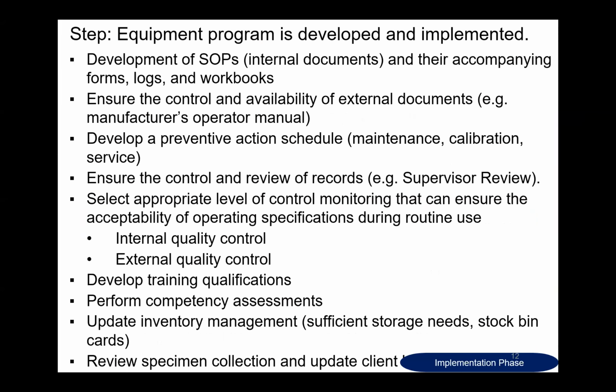Okay, so for new equipment, the lab will now need to implement an equipment program. An equipment program will be guided by several documents. One of the documents that the lab will now start developing is SOPs, standard operating procedures. The source of SOPs is usually manufacturer manuals. So the SOP would dictate how to operate a machine. It's a step-by-step method of how to operate the machine.